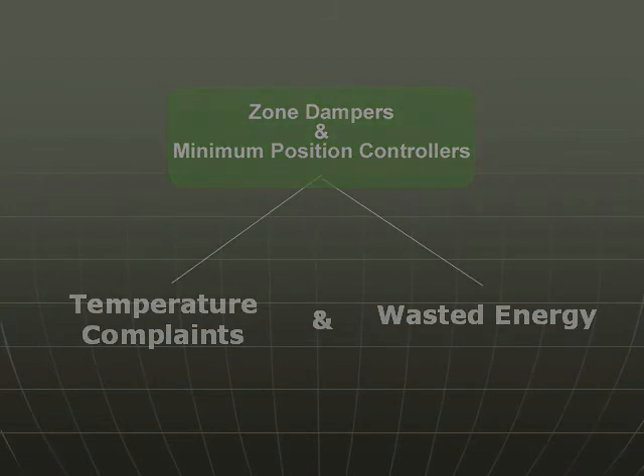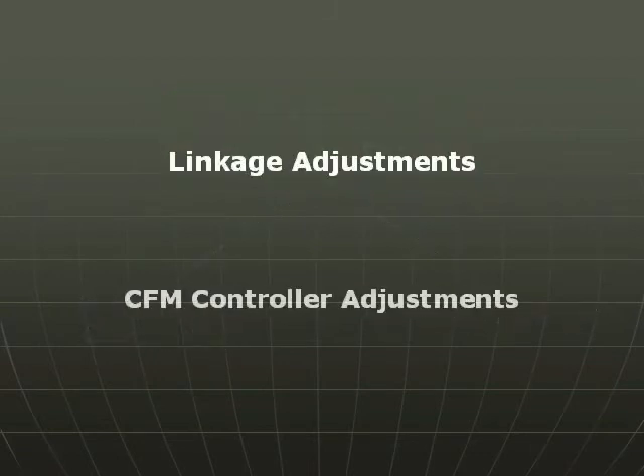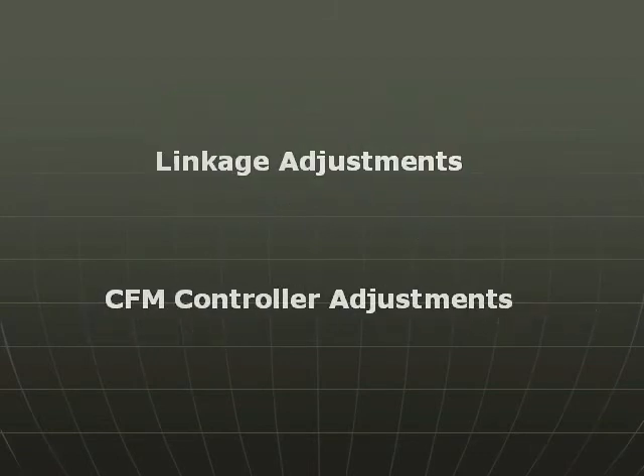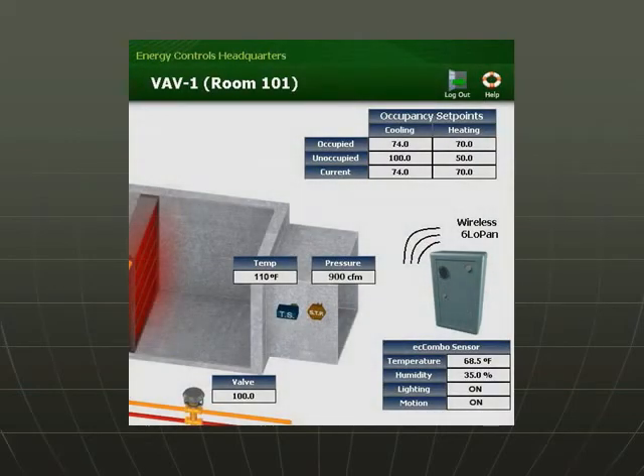Zone dampers and minimum position controllers often cause temperature complaints and wasted energy. Linkage adjustments and CFM controller adjustments are two common problems within the thermostatic zones. Monitoring the room temperature, supply air, and CFM allows the building operator to diagnose defective conditions, stop the energy waste, and improve temperature conditions.